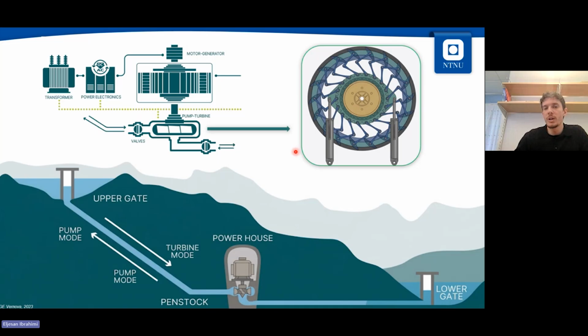In this way, we can also have a fast transition time from generating to pumping mode, because we don't have to disconnect the machine from the grid. We can stay connected with the converter and supply the grid with reactive power, maintaining a stable voltage while transitioning from generating to pumping, or vice versa.